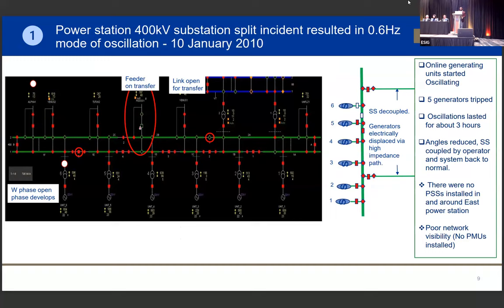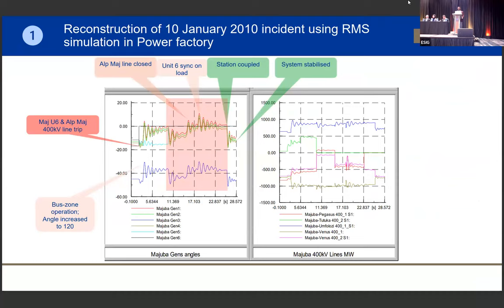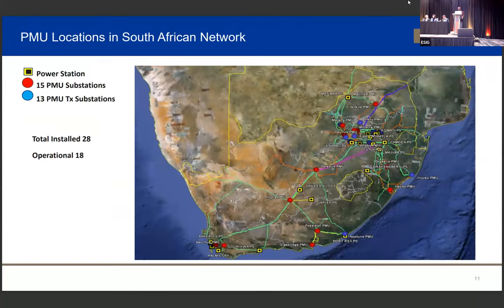From the findings, we didn't have power system stabilizers installed in and around East power station, and we had poor visibility because we didn't have PMUs installed. After the event, we simulated using RMS simulation in PowerFactory, because this was one of the biggest incidents. So we installed PMUs across the country, a total of about 28, and 18 are online.